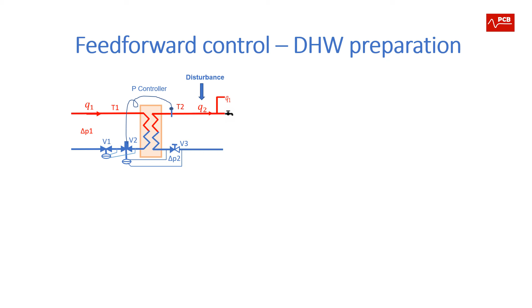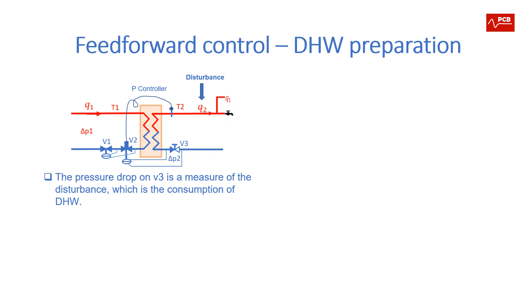Feed-forward control. We have here a process of domestic hot water preparation, instantaneous hot water preparation, and a mechanical P controller. And the system works in this way. The pressure drop on the secondary side on the valve V3 depends on the flow on the secondary side. It means it depends on consumption. And if the consumption increases, for example, then the pressure drop on this valve increases, and this pressure increase is transmitted to the primary side and opens the valve on the primary side V2, and therefore reacts on the disturbance before the controller can sense or detect that there was a drop in temperature. So we have a proactive operation of the controller.